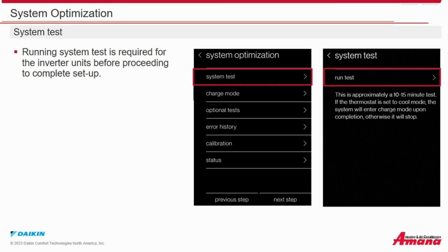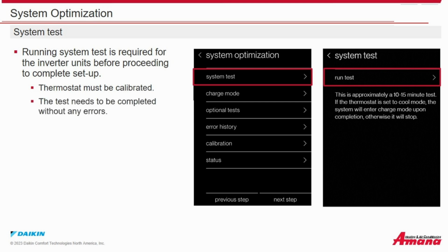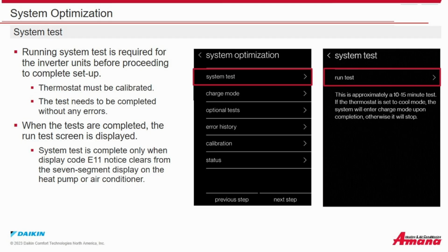System optimization. System test. Running system test is required for the inverter units before proceeding to complete setup. The thermostat must be calibrated. The test needs to be completed without any errors. When the tests are completed, the run test screen is displayed. System test is complete only when the display code E11 notice clears from the 7-segment display on the heat pump or air conditioner. System must be in the off mode while running the test for the E11 code to clear.